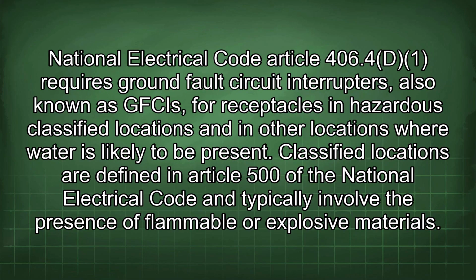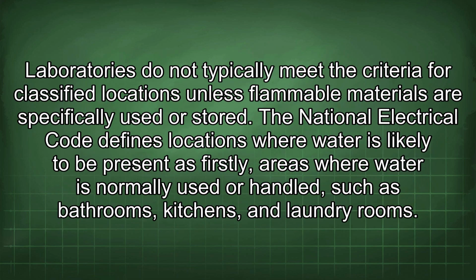National Electrical Code Article 406.4 requires ground fault circuit interrupters, also known as GFCIs, for receptacles in hazardous classified locations and in other locations where water is likely to be present. Classified locations are defined in Article 500 of the National Electrical Code and typically involve the presence of flammable or explosive materials. Laboratories do not typically meet the criteria for classified locations unless flammable materials are specifically used or stored.